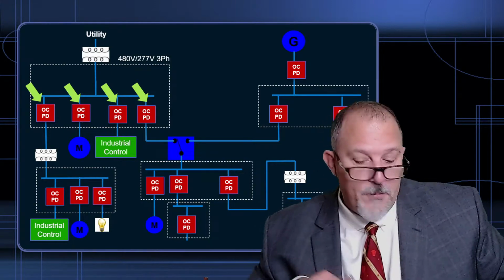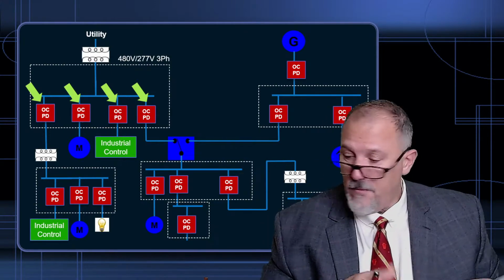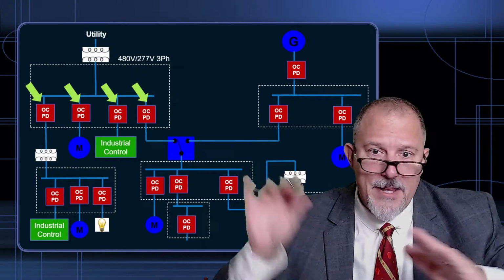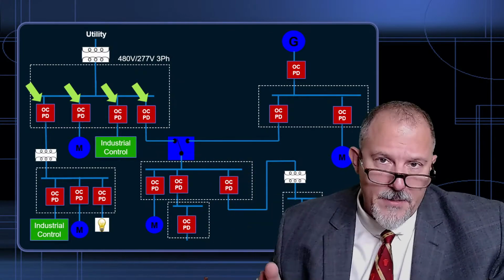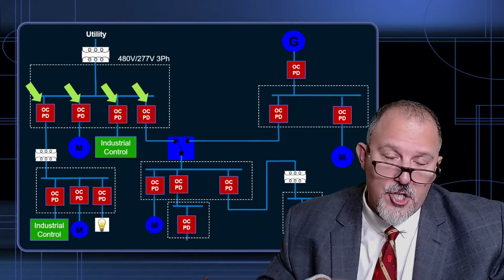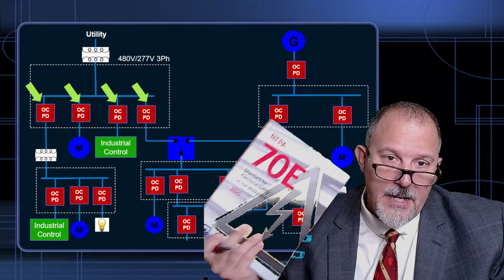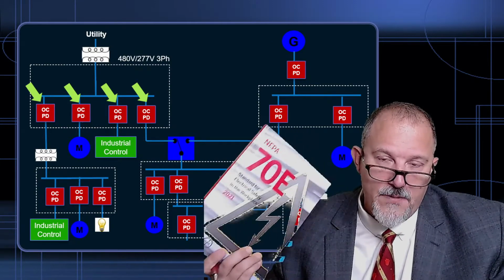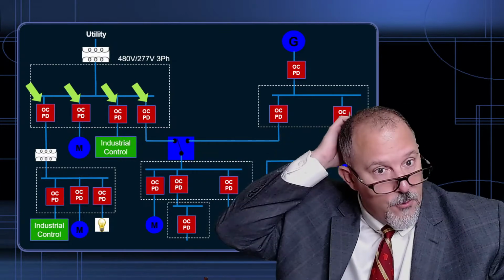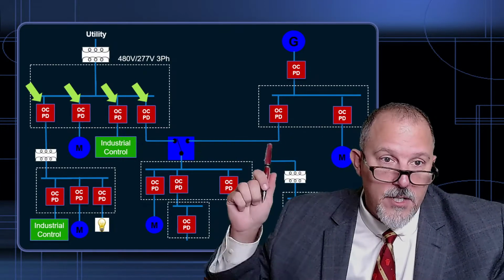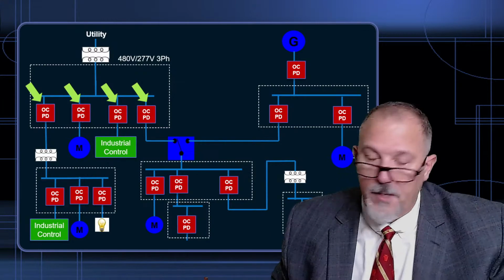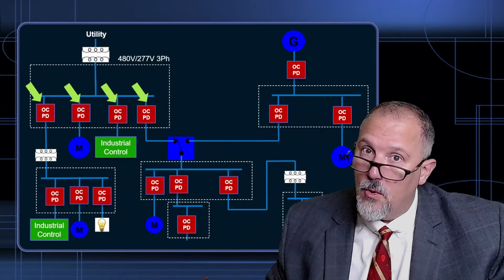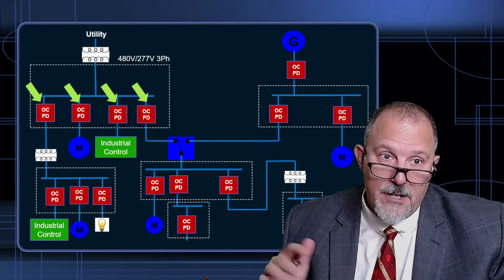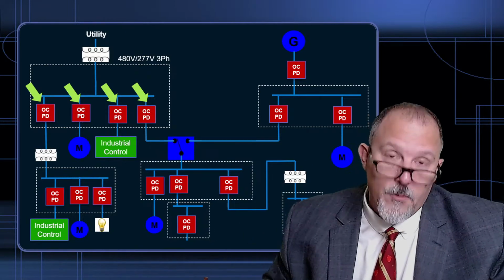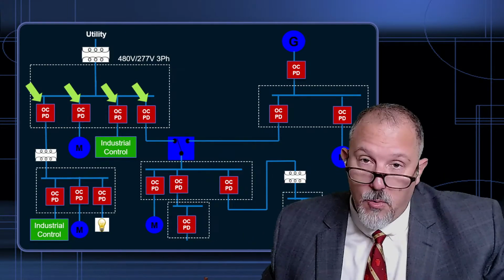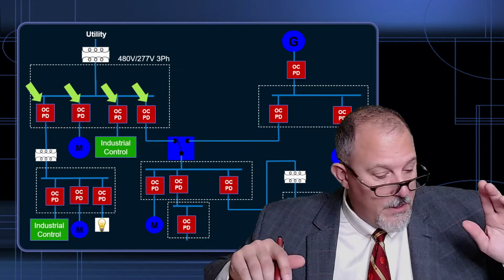So I would always tell people in the 2017 or the 2020 code, don't do this. That's an easy way out, to say I'm going to put the clearing time and the available fault current. What you really should do is follow 70E and create a label in accordance with 70E. Find a qualified person to do that for you and label that equipment, because that individual is going to be using tools like IEEE 1584 and others to calculate the incident energy in that equipment. And it will be done, hopefully, correctly if you have a good qualified person doing that.